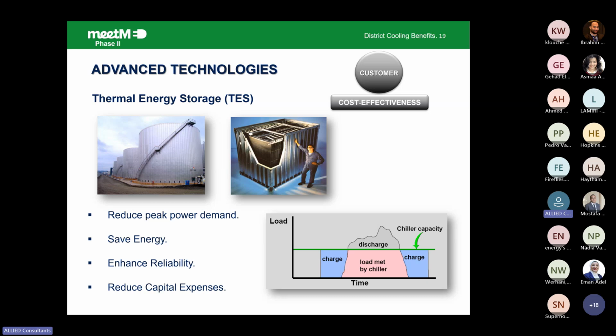And definitely, we can run the thermal storage in non-peak hours. We can run the thermal storage by days or by night, depending on the area served. Let us say we have an apartment building, so we can run the chillers by day and store the energy, and then by night we can switch off all the cooling towers and avoid any noise by night. On the contrary, if you have an office building, then we are storing the energy by night, and then we are consuming it by day. As I said, next page.